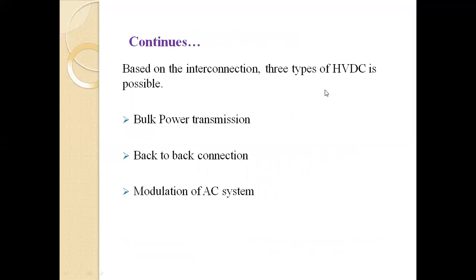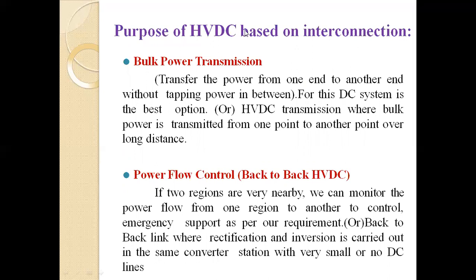So there are three types of HVDC application possible. First, bulk power transmission. Second, back-to-back connection, and third, modulation of the AC power. The purpose of HVDC, based on interconnection, is first bulk power transmission. We transfer the power from one end to another end without tapping power in between. For this, the DC system is the best option, or HVDC transmission, where the bulk power is transmitted from one point to another point over a long distance.